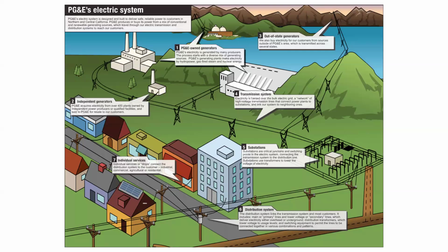By definition, there's going to be periods of time where we can squeeze more power out of the grid and transmit more energy through the system. But when we made our baseline assumptions, these were based off the 99th percentile day that the territory experiences. There are going to be times by design where we exceed those temperatures, and during those periods we should be throttling down our assets, because otherwise we can degrade them or risk overheating our lines and sagging them closer to the ground as they heat up. So we're trying to build a more efficient grid that pumps more when we need it and throttles back when appropriate. Thank you.